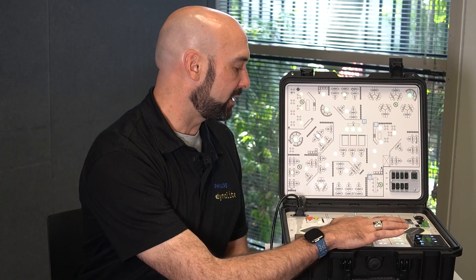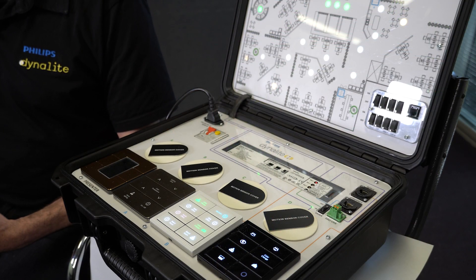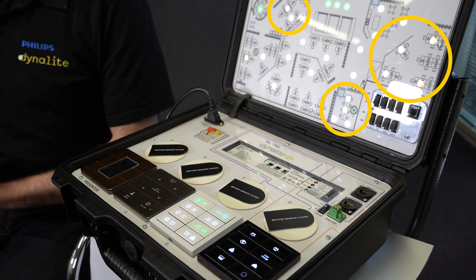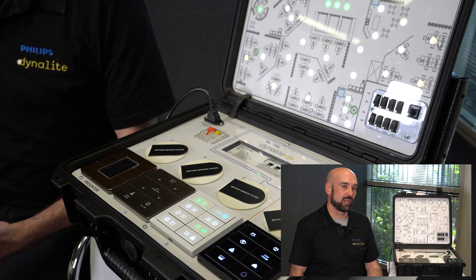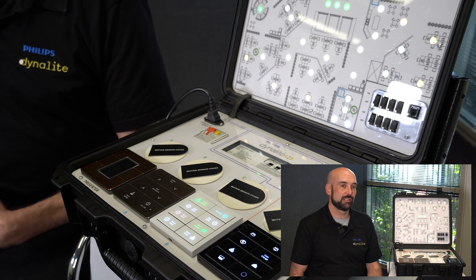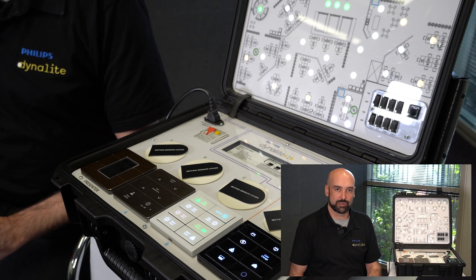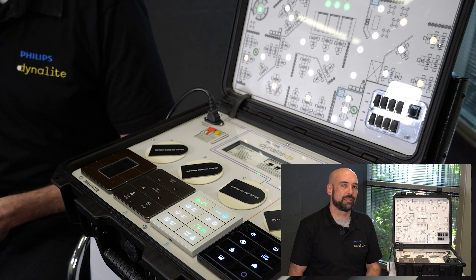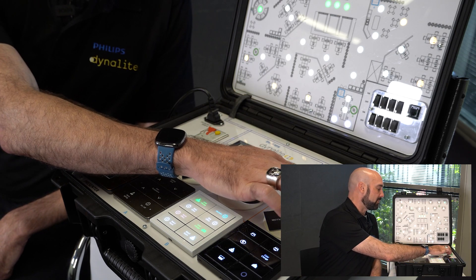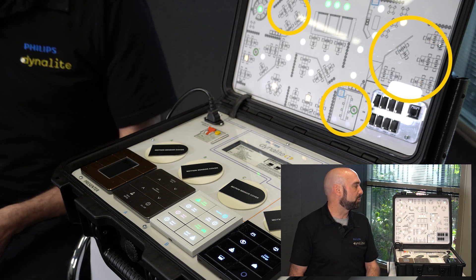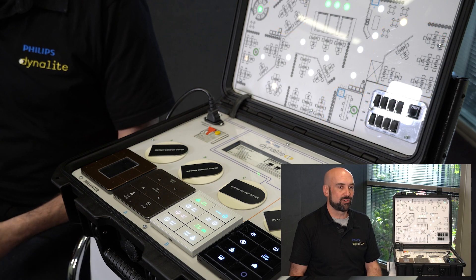Turning off a few areas, we can demonstrate emergency response. The system picks up a dry contact input from an emergency system and turns all lighting on. Once the emergency response message is received, none of the user interfaces can switch off the lighting — preventing accidental switching off in a panic situation and ensuring occupants can see their way out. When the emergency passes, the dry contact is released and the system returns exactly to what it was doing previously.